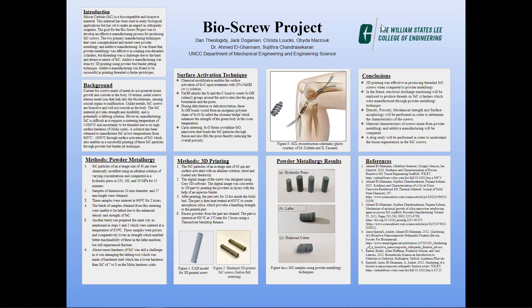The two primary manufacturing techniques that were conceptualized and tested were powder metallurgy and additive manufacturing. It was found that powder metallurgy was effective in creating non-threaded cylinders, but threading was a challenge due to the hard and abrasive nature of silicon carbide. Additive manufacturing was done by 3D printing using powder bed binder jetting technique, and was found to be successful in printing threaded cylinder prototypes.